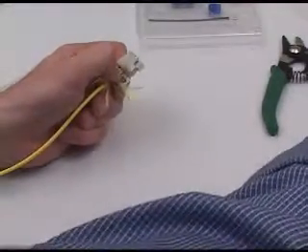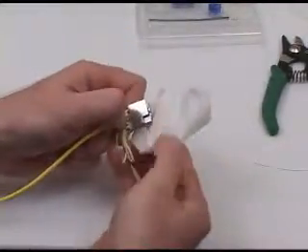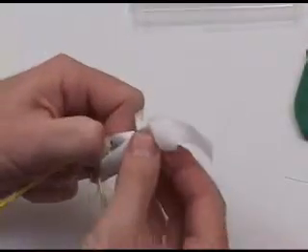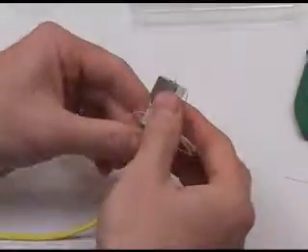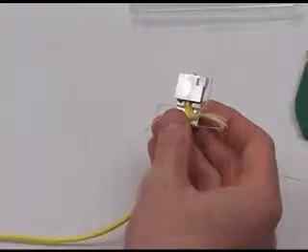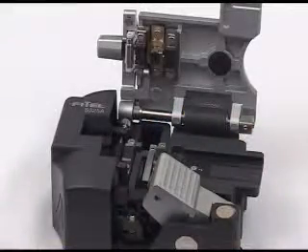Once the bare fiber is exposed, clean the fiber to remove all of the residue left by the 250 micron jacket. Using a moistened alcohol wipe, wipe the fiber in an outward direction away from the holder and when all of the residue is removed, the fiber will produce a squeaking sound.